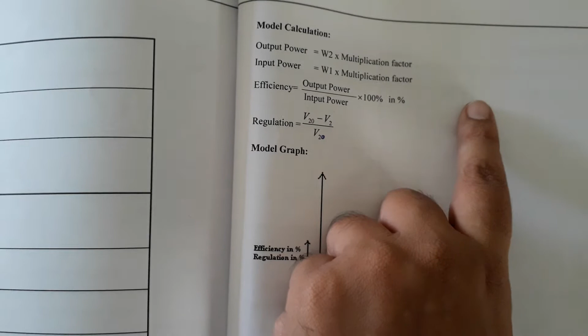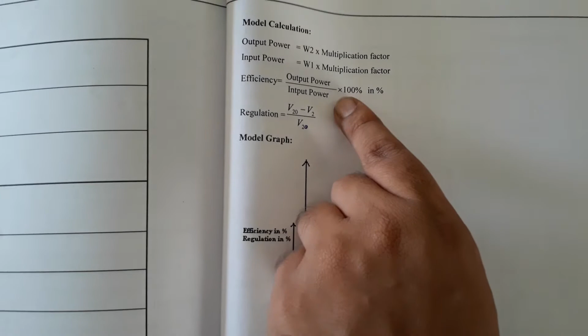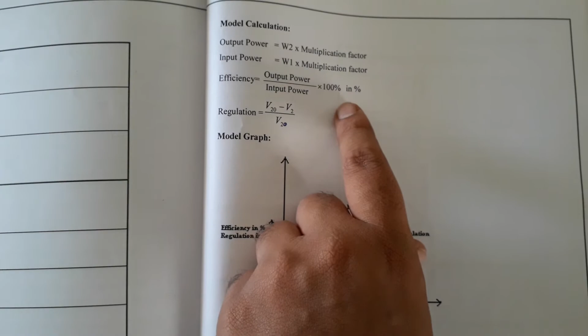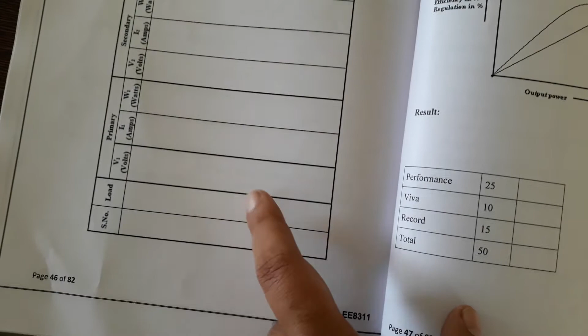So what is the corresponding efficiency for the particular load? For 0.5 amps, what is the efficiency? For 1 amp, what is the efficiency? For 2 amps, what is the efficiency? For 3 amps, what is the efficiency? So you can calculate up to 4 amperes, because up to the 4 amperes load, you are giving the load to the transformer. Up to the 4 amperes load, you can calculate the corresponding efficiency.